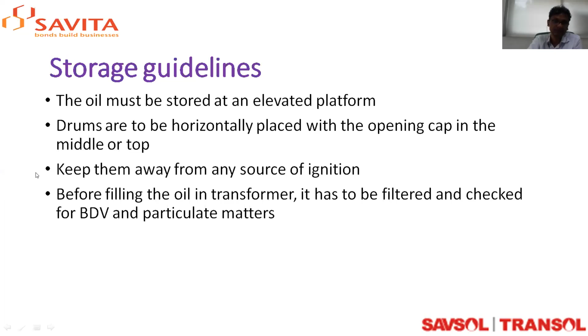It should not be stored in the rain, meaning rain should not fall directly on the drums. That will be beneficial. Or if you are storing in an open area, you can put tarpaulins on them in order to avoid the moisture increase. Before filling, one has to do the filtration, because when you are doing the filling, there is a tendency for the moisture to increase, and when this moisture goes to the transformer directly, it is going to hamper the electrical properties, as well as that moisture will transfer from the oil to the paper, and it will be retained in the paper. So if you do the filtration before this, that will always be helpful. Next slide.